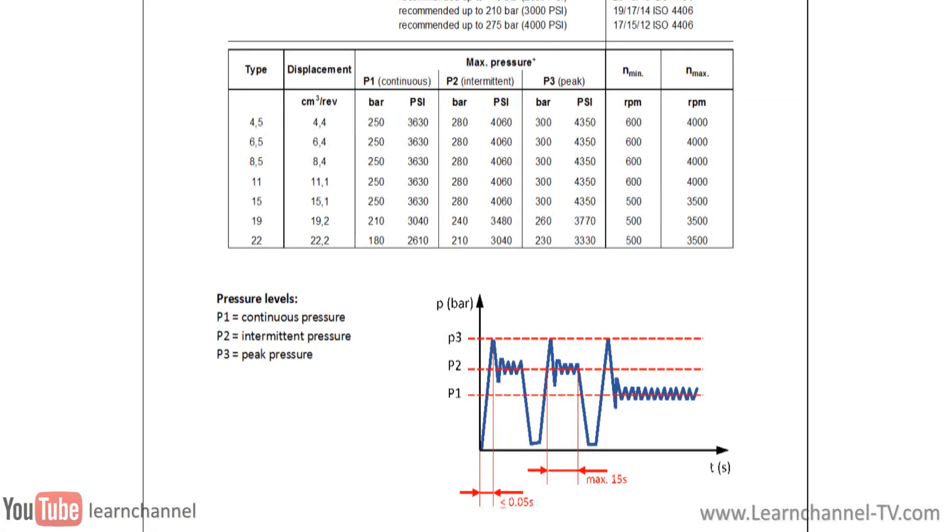Also interesting, this table distinguishes between three pressures. Peaks in pressure can occur due to external load, for example. A check valve at port P or a surge tank can protect the pump from the pressure peaks.